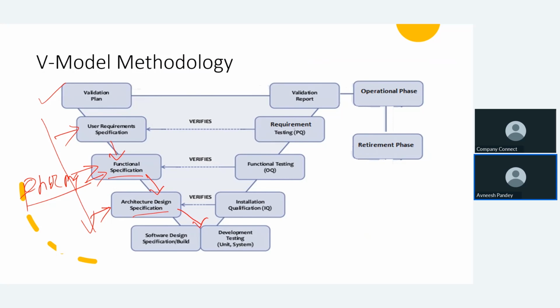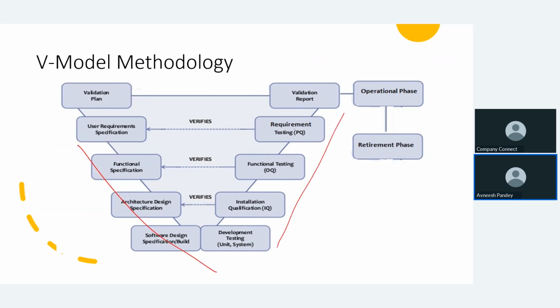After development, testing. As part of testing, we have IQ, OQ, PQ. Correct. IQ has to verify against the design specification, OQ has to verify against the functional specification, and PQ has to verify against the URS. So why is it called the V model? Because its shape is kind of a V actually. Here the mandatory thing is what? IQ has to verify against the design, OQ has to verify against the FS, and PQ has to verify against the URS. That's why the shape becomes a V. Correct. So verification is necessary. It's mandatory here.